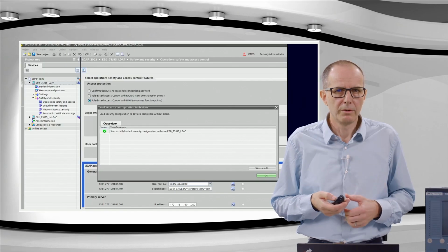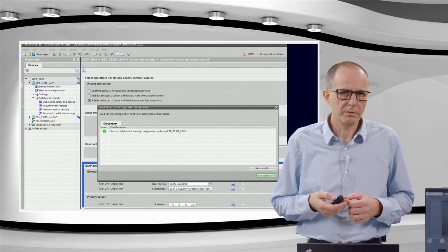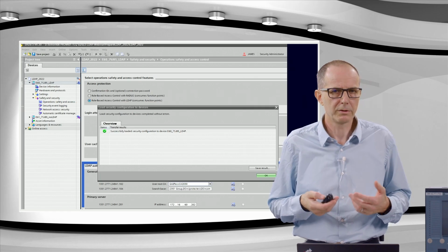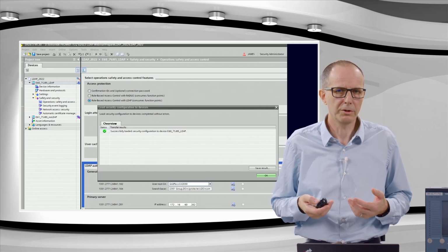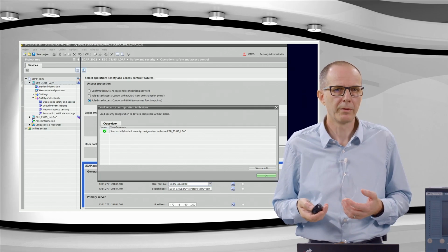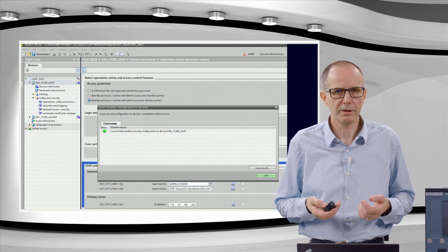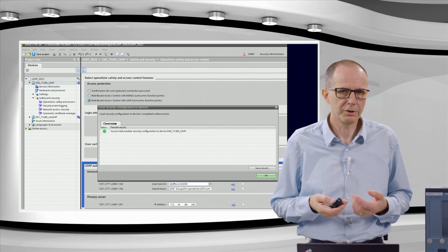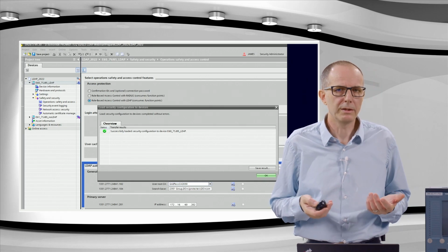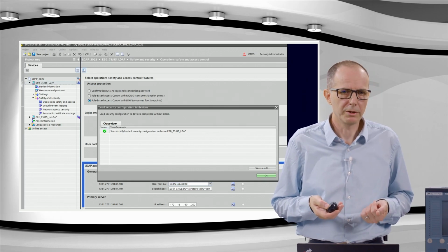The Ethernet connection from the device to the Active Directory is okay, and the user is included in the Active Directory user group with a role ID according to IEC 62351. The access control settings are successfully loaded to the device. So with DIGSI 5 as well-known SIPROTEC 5 engineering tools, you also can easily set the LDAP configuration.